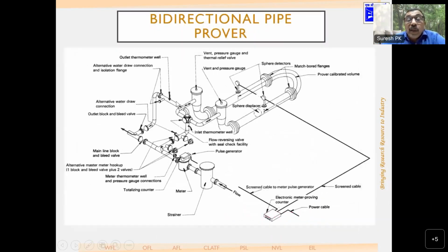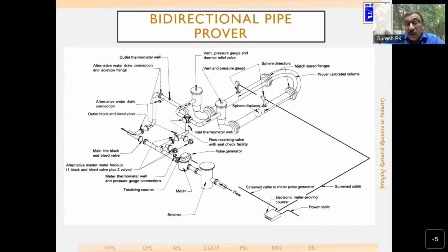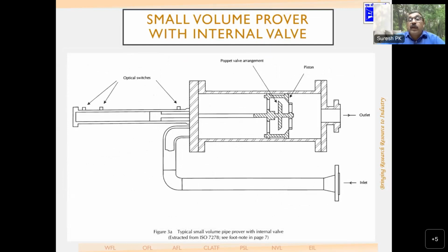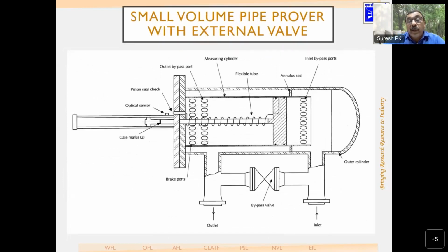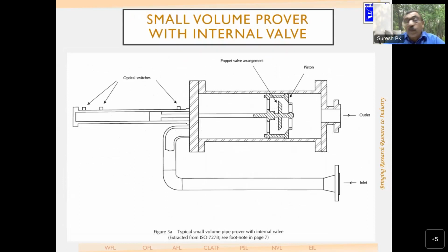Then you have the bi-directional prover. A bi-directional prover can move in both directions, and here the ball can move from here to here as well as here to here. The only thing is you divert the flow at this point. There is a diverter valve which will divert the flow from one direction to another when it comes here. So the principle is the same. The installation of this prover and the space required for it are very high. Therefore, small volume provers have been developed with internal valve and then external valve. The principle is the same: whatever is passing through the meter is passed through a calibrated prover volume, and then you compare the volume of the prover with the volume of the meter.